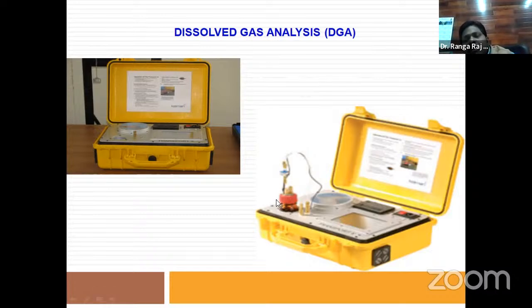Moisture can enter at any level during the process. Once moisture enters, the result will be different, so relying on this test alone is not good for accurate assessment. We have to perform some additional 2 to 3 tests along with this. But if performed accurately and systematically, the result from this test is very useful in deciding the health status of a transformer.